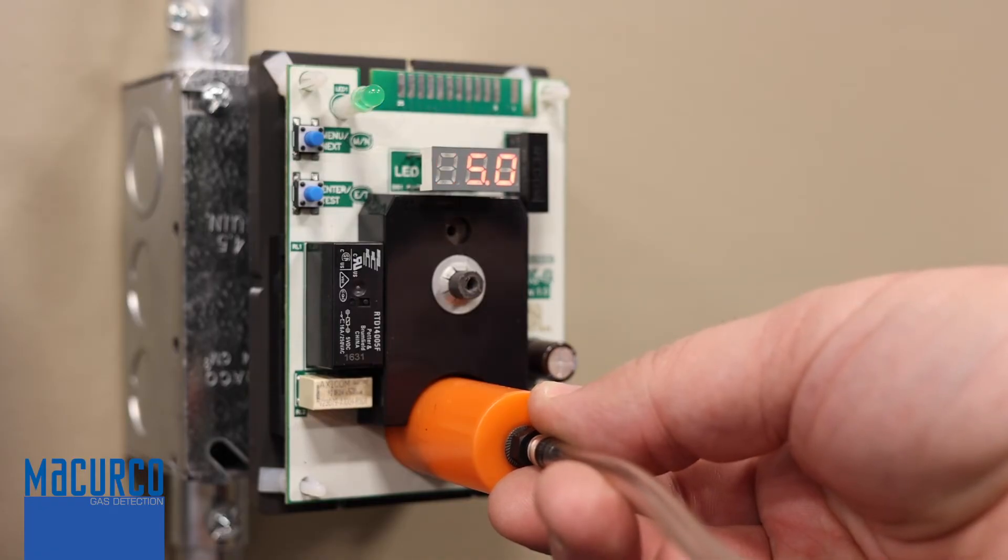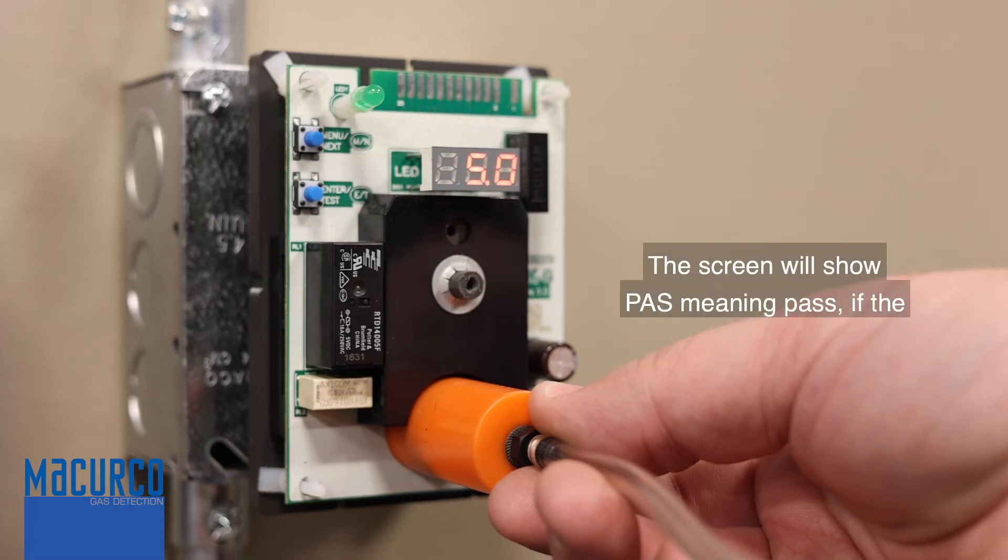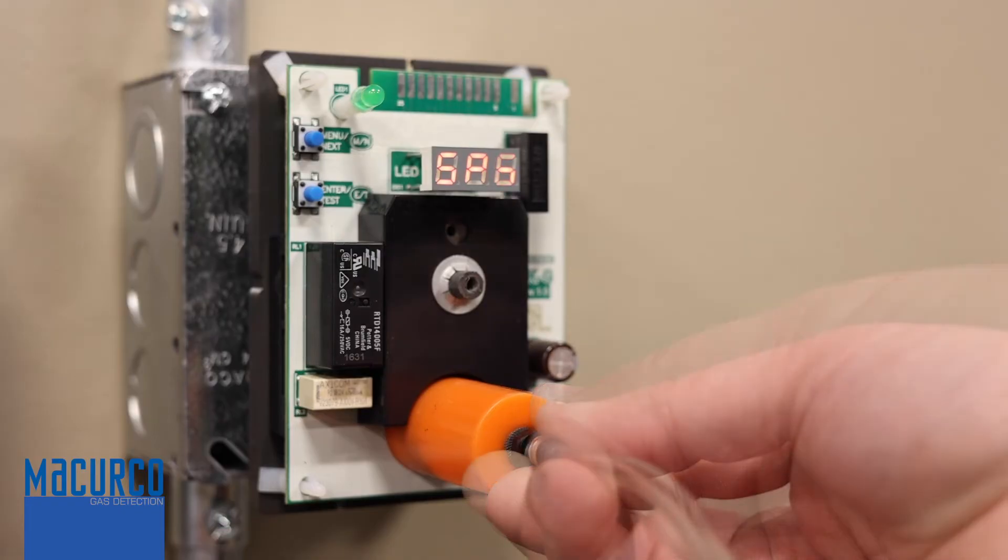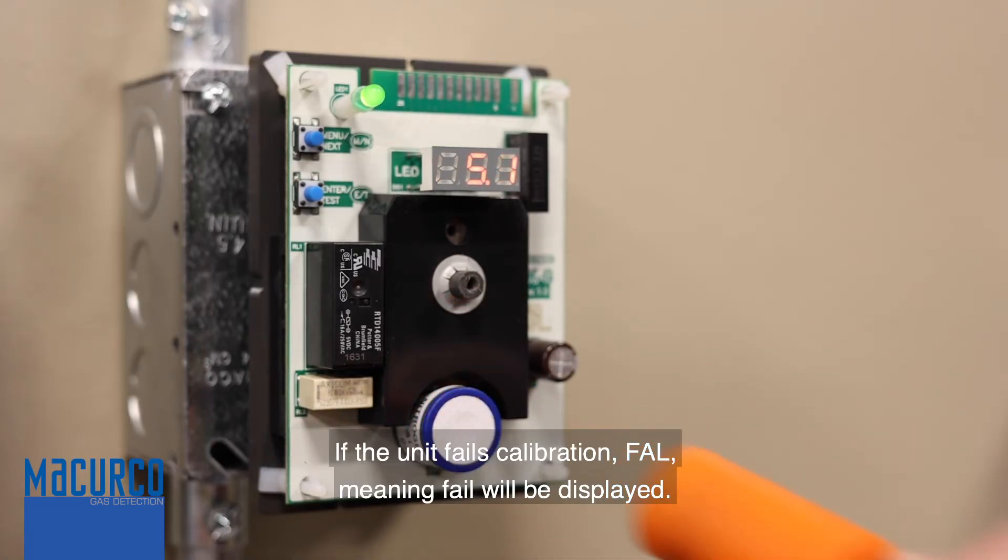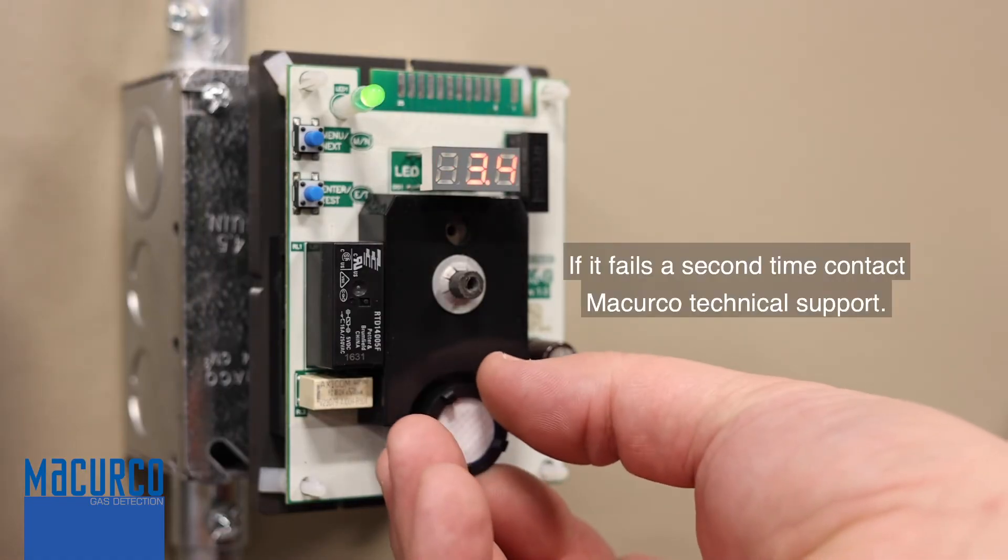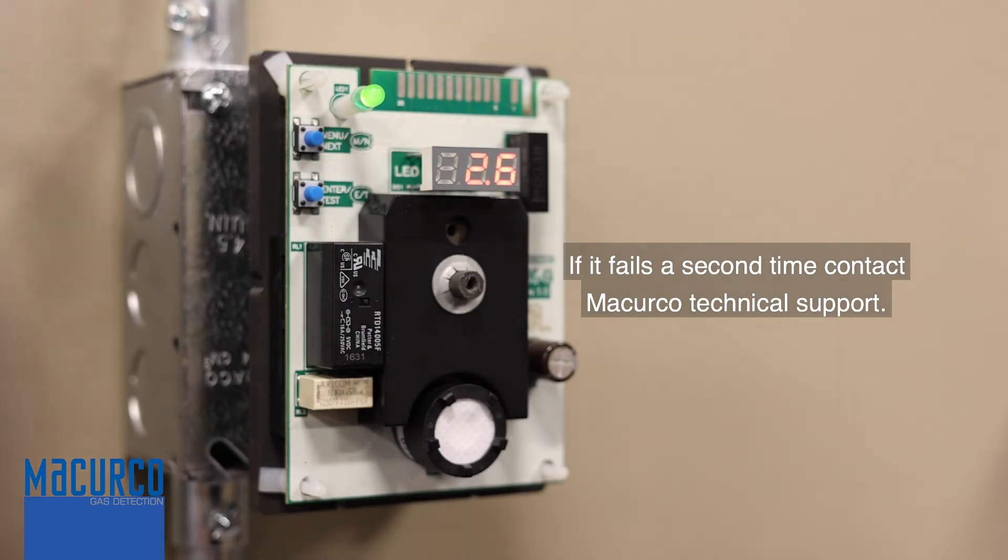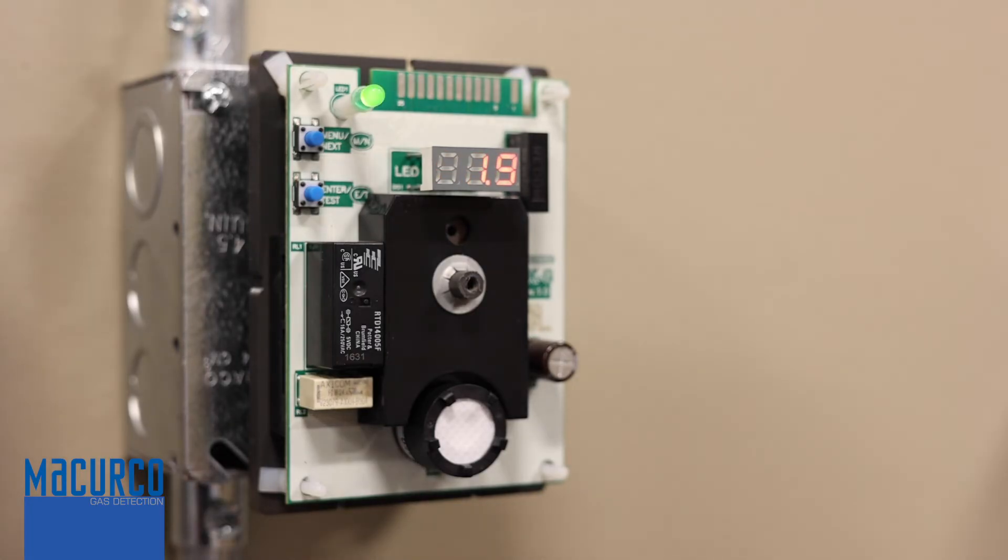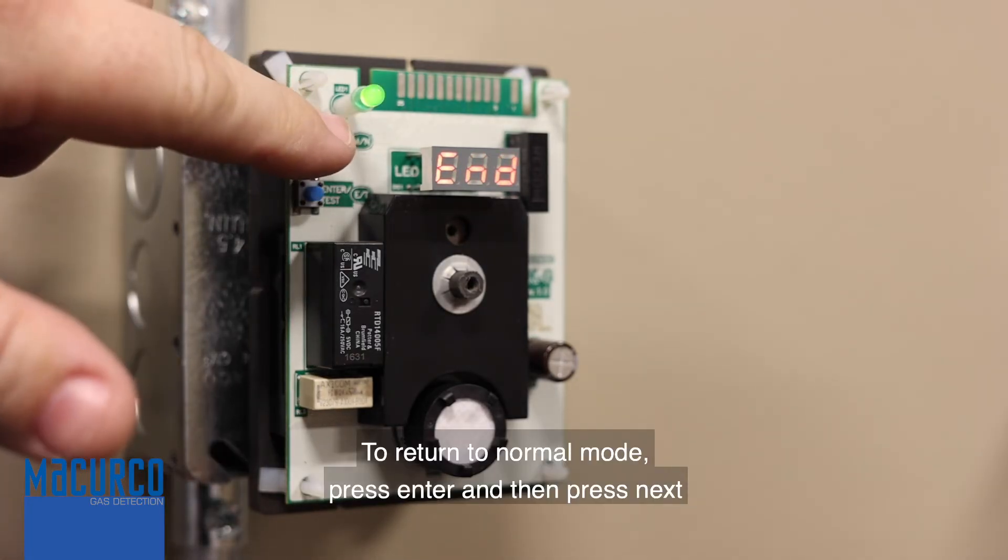The screen will show pas, meaning pass, if the calibration is successful. If the unit fails calibration, fal meaning fail will be displayed. If it does fail, repeat the steps over from the beginning. If it fails a second time, contact Macurco technical support. To return to normal mode, press enter and then press next until end is displayed.